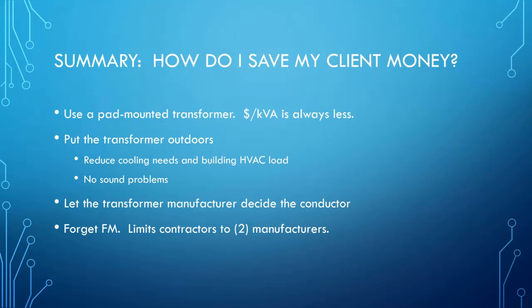Three-phase pad mounted transformers, because of the volume that they're purchased by utilities, there are manufacturers who are used to stamping out sometimes 75, 80, 100 transformers per day of pad mounted units. So for that reason, and that reason only, the dollars per kVA is less when purchasing a pad mounted transformer. It's just a fact of life.